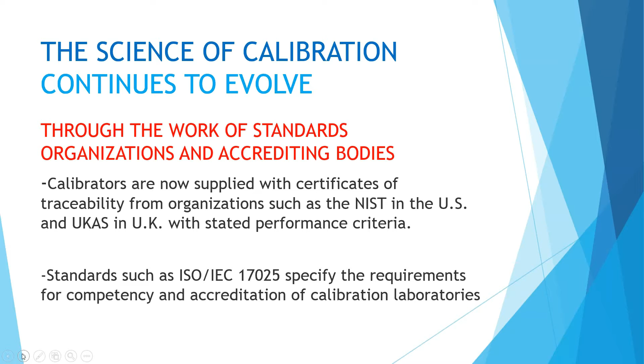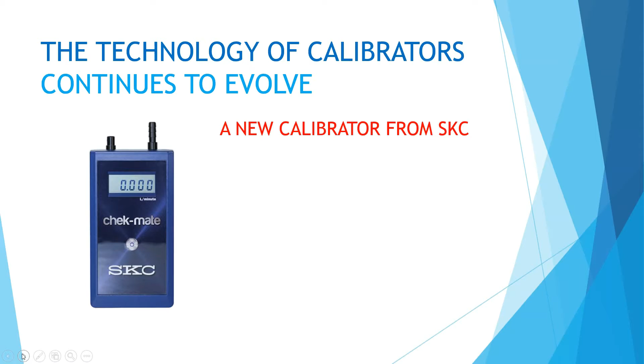Now, the technology of calibrators also continues to evolve. I would like to introduce you to a brand new calibrator from SKC. Since many of our pumps incorporate the name AirCheck, this calibrator has been given the clever name of Checkmate. Or in Australia, we could call it the good on you mate. It is an orifice-type flow meter that uses a differential pressure sensor. Okay. Simply put, the delta P is proportional to the airflow. It has an accuracy of 1%, thus meeting the definition of an intermediate standard we've just all learned.